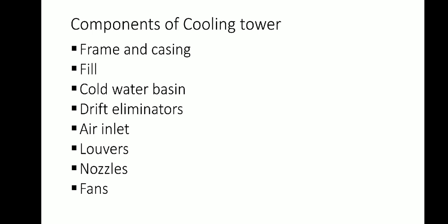The cold water basin, located at or near the bottom of the tower, receives the cooled water that flows down through the tower and fill. The basin usually has a sump or low point. In some forced draft counterflow designs, however, the water at the bottom of the fill is channeled to the perimeter, which functions as a cold water basin. Propeller fans are mounted beneath the fill to blow the air up through the tower. With this design, the tower is mounted on legs, providing easy access to the fans and other motors.